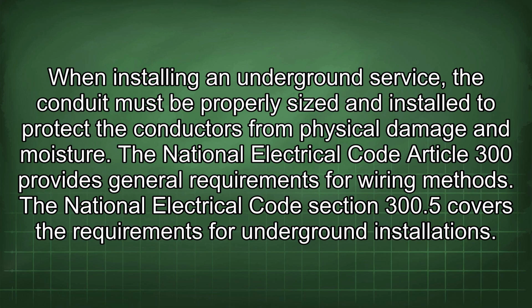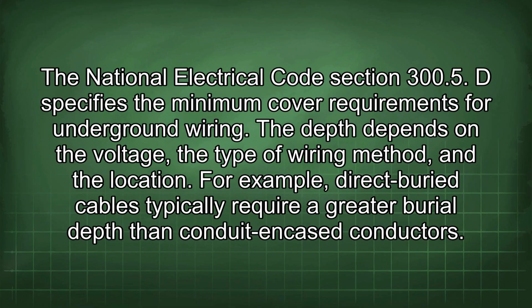When installing an underground service, the conduit must be properly sized and installed to protect the conductors from physical damage and moisture. The National Electrical Code Article 300 provides general requirements for wiring methods. Section 300.5 covers the requirements for underground installations. Section 300.5 D specifies the minimum cover requirements for underground wiring. The depth depends on the voltage, the type of wiring method, and the location. For example, direct buried cables typically require a greater burial depth than conduit encased conductors.